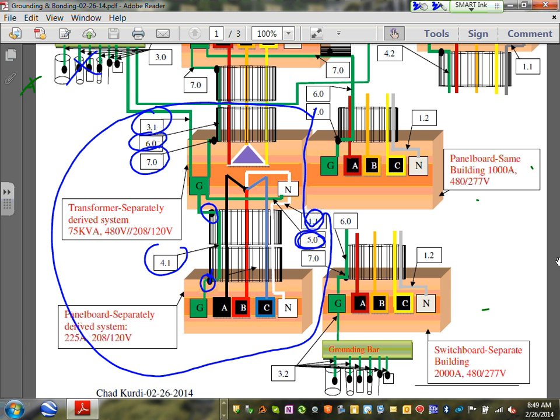Typically what we do, guys, the industry standard is inside the transformer. If you open it, you'll see a bond. You have to install a bonding wire between the neutral bar and the ground bar inside the transformer. Okay, any comments, guys? Any questions? I want to focus on sizing these ones for the separately derived system. So I want to focus on this and this and this and this and this, basically, and this one. These are the ones I'm going to size. This would be the receptacle panel that you guys have, and this would be the 208/120 transformer. Remember the 208/120 transformer that we have for the 208/120 bus duct?